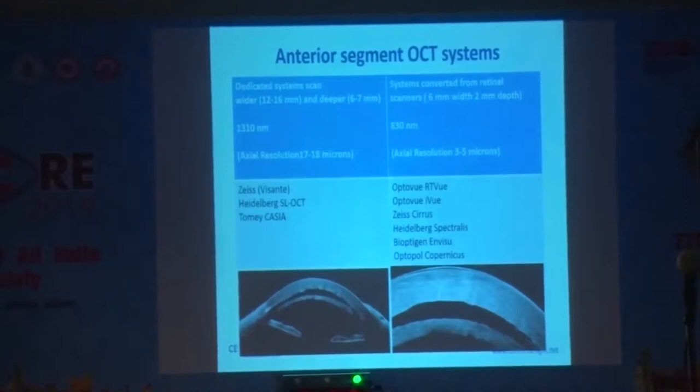Just a brief about the existing AS OCT systems. Currently, we have two types: dedicated anterior segment OCT systems and those converted from retinal scanners. The dedicated systems use a wavelength of 1310 nanometers and provide wider and deeper scans, compared to converted retinal scanner systems that use 830 nanometers and provide shorter scans but with much higher resolution.